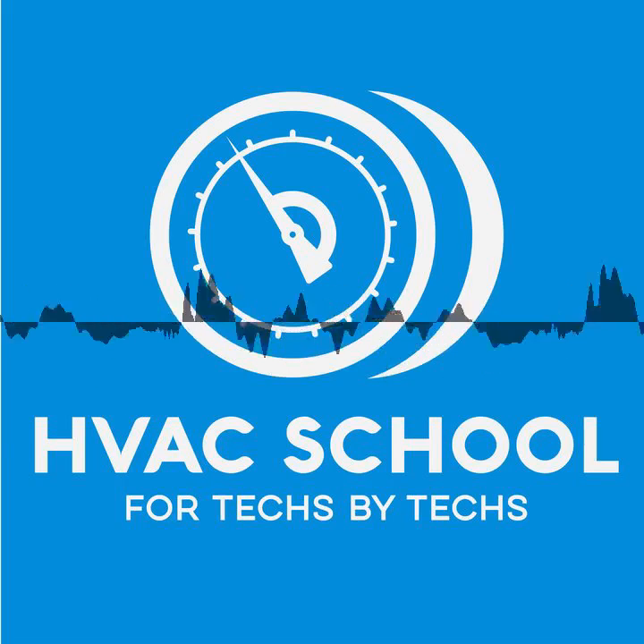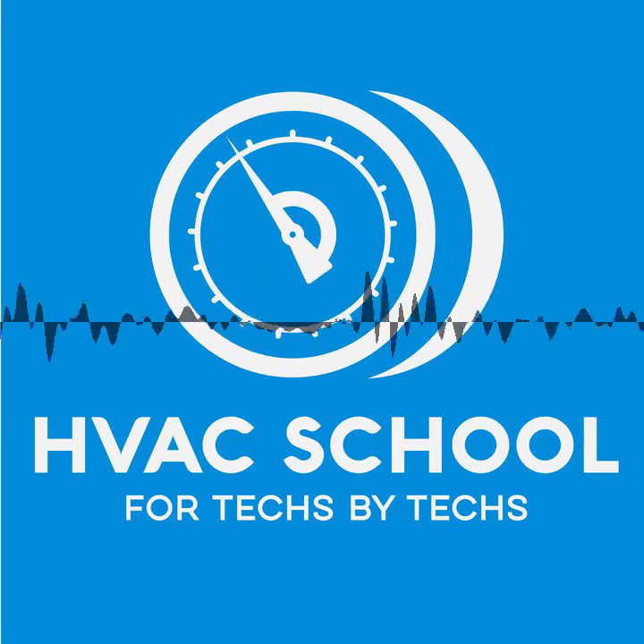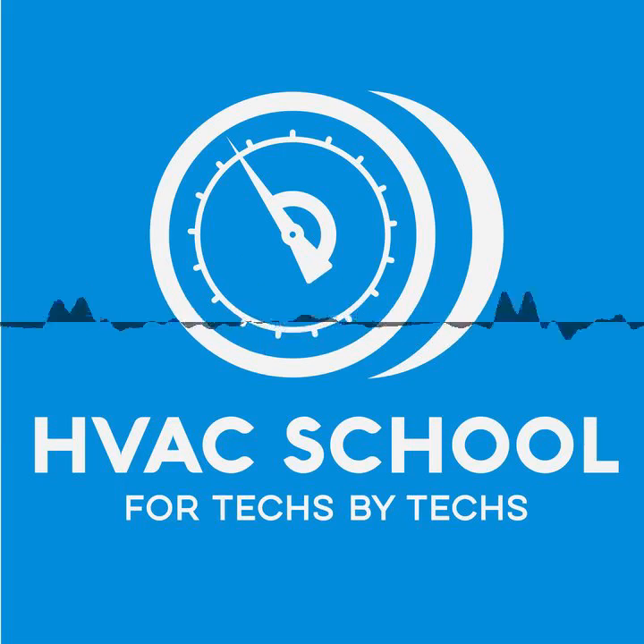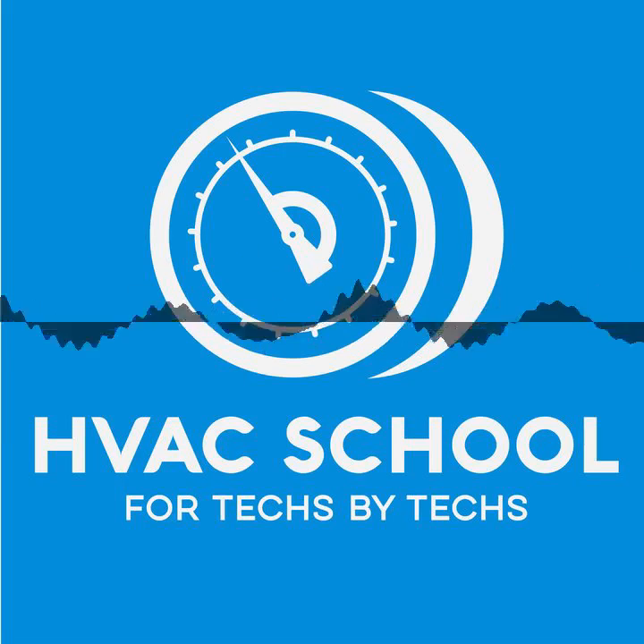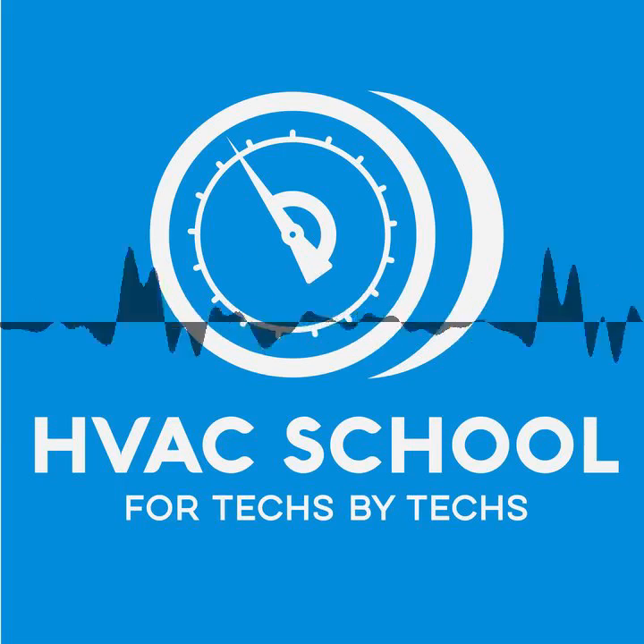I guess I need to address this because I've said on this podcast before, I've called a TXV a constant superheat valve, and frankly, I never considered the idea that you do have increased spring compression and the fact that there's always going to be a lag in response. So your superheat actually has to increase for that valve to open, which makes perfect sense.